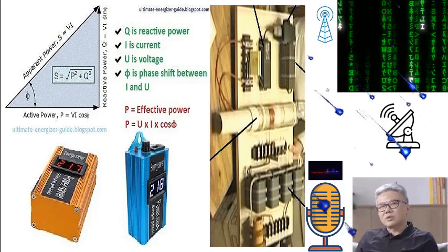Capacitors. Capacitors are a simple and widely used solution for reactive power compensation. By causing the current to lead the voltage, capacitors generate reactive power to supply the grid. Advantages. Capacitors are easy to maintain, have no rotating parts, and are cost-effective, especially for small and medium loads. They can also be adjusted according to the evolving power requirements of the load.